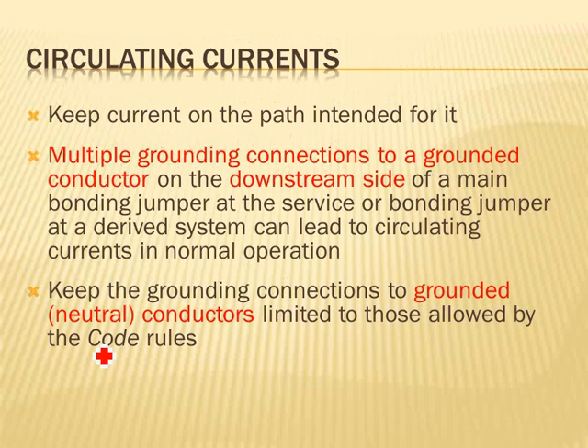Circulating current: you hear a lot about keeping the current on the path intended for use. That's what they talk about with circulating current, multiple grounding connections to a grounded neutral downstream of the service. That's why you don't bond the neutral. Keep the grounding connection directly here.